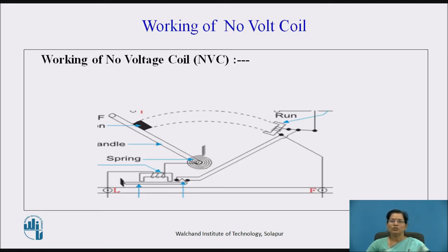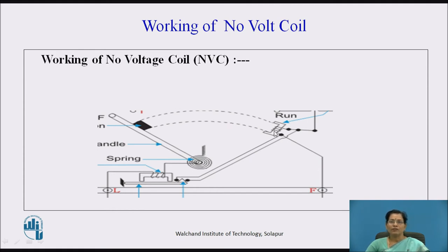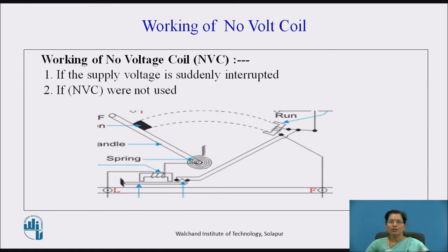Let us see about the working of the no-volt coil. When current flows through this coil, the no-volt coil creates a magnetic field, and when we move this arm from the first position to the run position, due to this magnetic field, the arm remains at that point. But if the supply voltage is suddenly interrupted, then this no-volt coil demagnetizes, and due to the spring action, this handle moves to the off position.